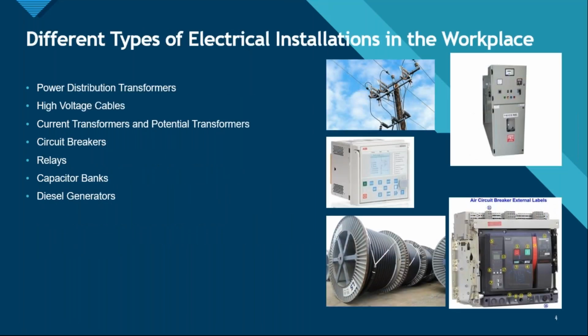Then, different types of electrical installations that you can find in the workplace, right? The first and foremost thing that you can find is the power distribution transformers, the huge transformers in the substation at your workplace, right? Those are very high voltage transformers, at least 11 kV transformers, right? Since there is 11,000 volts going through it, that voltage is stepped down for industrial use, right? So if those transformers are not taken proper care of, huge disasters can happen.